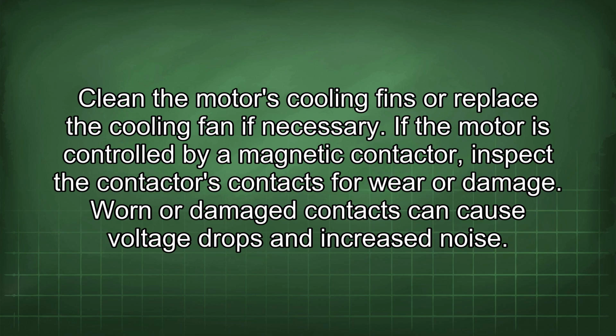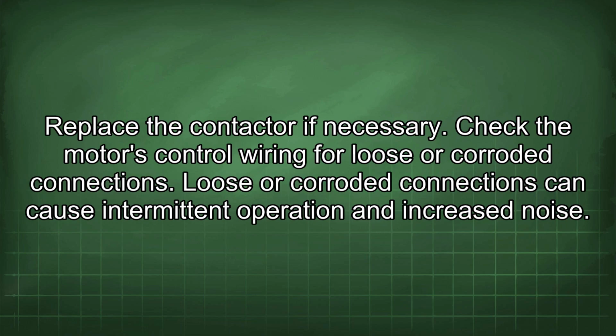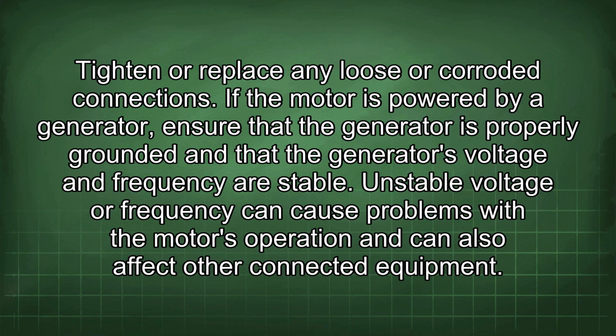If the motor is controlled by a magnetic contactor, inspect the contactor's contacts for wear or damage. Worn or damaged contacts can cause voltage drops and increased noise. Replace the contactor if necessary. Check the motor's control wiring for loose or corroded connections. Loose or corroded connections can cause intermittent operation and increased noise. Tighten or replace any loose or corroded connections.